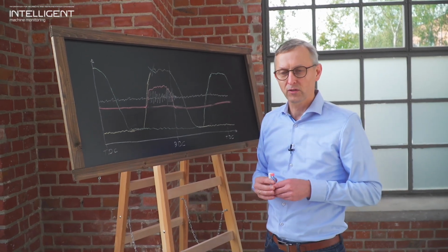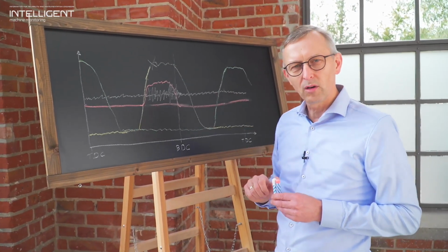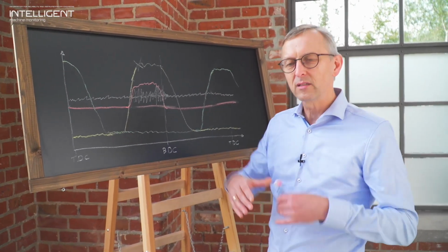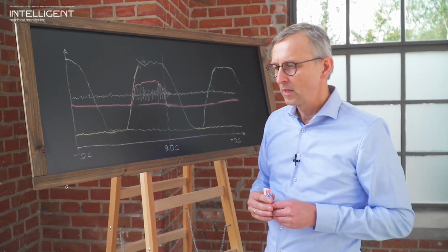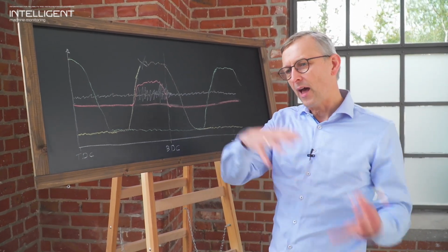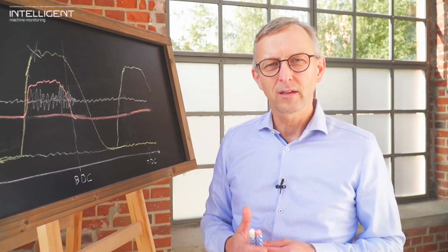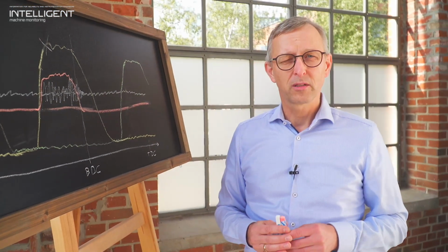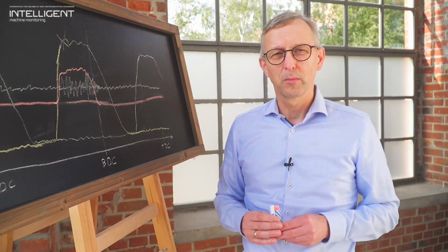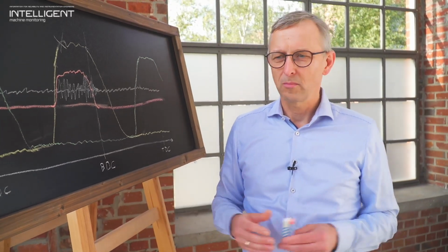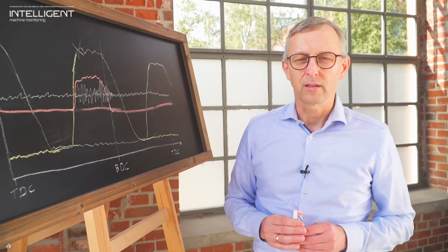realize that there's a significant problem coming up, and we can all imagine if this liquid builds up to a higher volume inside our pulsation damper, for example, then at some point a large volume of liquid can pass into our cylinder, and then we get a real liquid slug, which would then create a real massive mechanical problem in our machine, which may even lead to a complete loss of that machine, or at least of that cylinder.